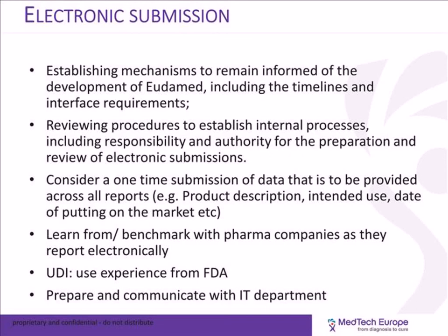Okay, we have a question here that just arrived. Let me read it. Does the risk management have to be performed for each device, or can it be performed for a device category? This is a very good question. Most of the regulation verbiage refers to device, so the PMS plan needs to be done by device. Now, our current interpretation is that we can probably extend that to device family, and this is to be discussed further with notified bodies.